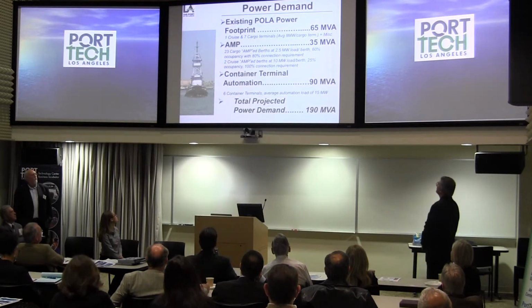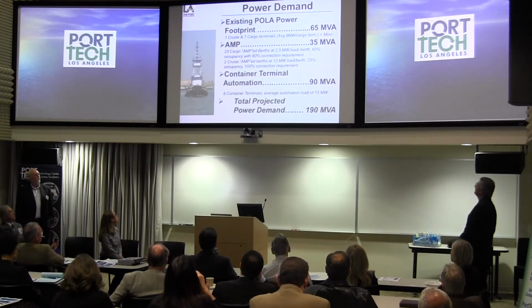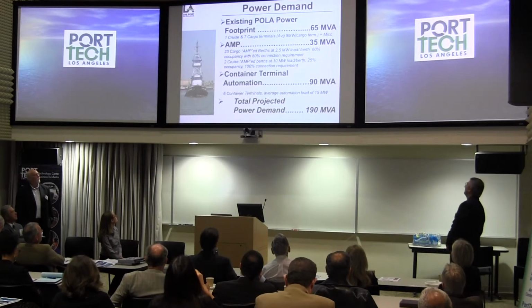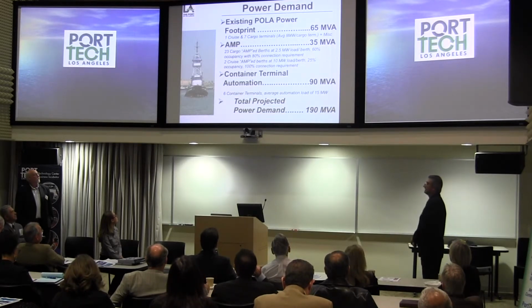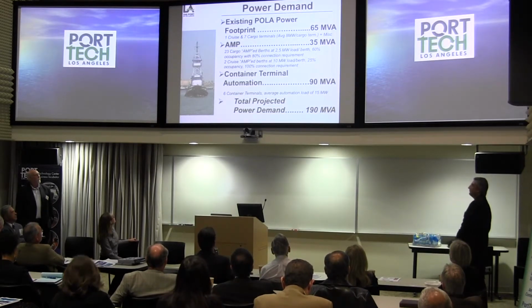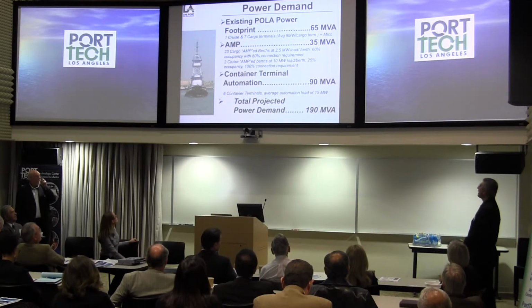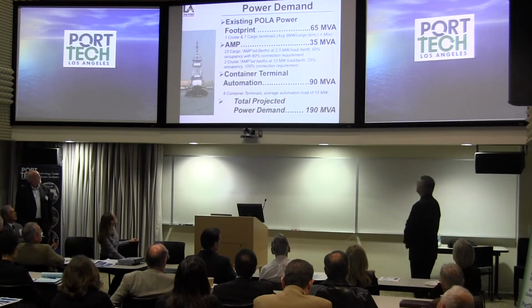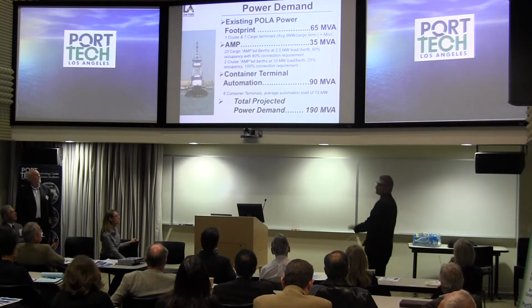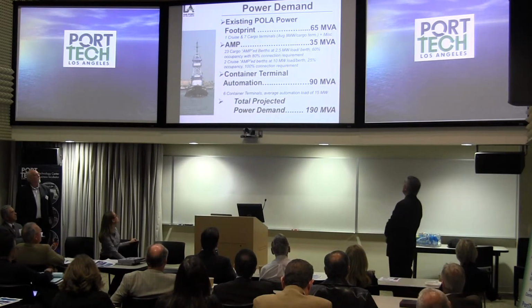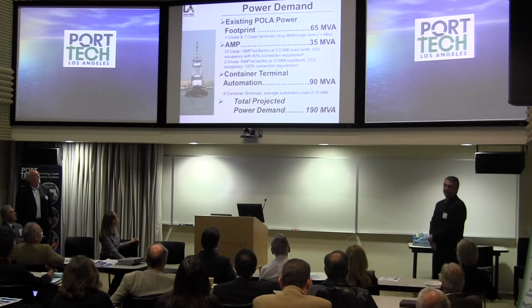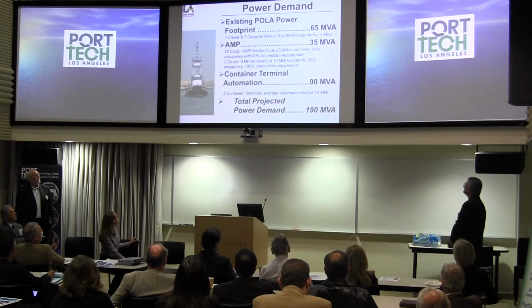As mentioned, the existing non-automated power footprint is estimated at 65 MVA. How do you estimate that? It's a simple formula. We have one cruise terminal and 7 cargo terminals. Our average cargo terminal is about 8 megawatts, non-automated. So if you add them up, it's about 65 MVA, plus or minus.